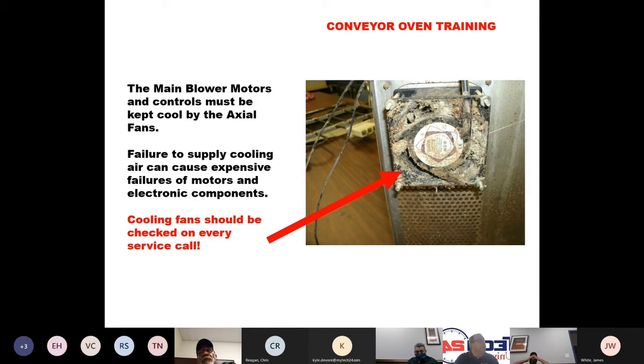The main blower motors and controls must be kept cool by axial fans. Here's a picture of a very, very dirty cooling fan. This cooling fan is probably so bad that if you have another fan, there's no reason to clean it, just replace it. You should check cooling fans on every service call.